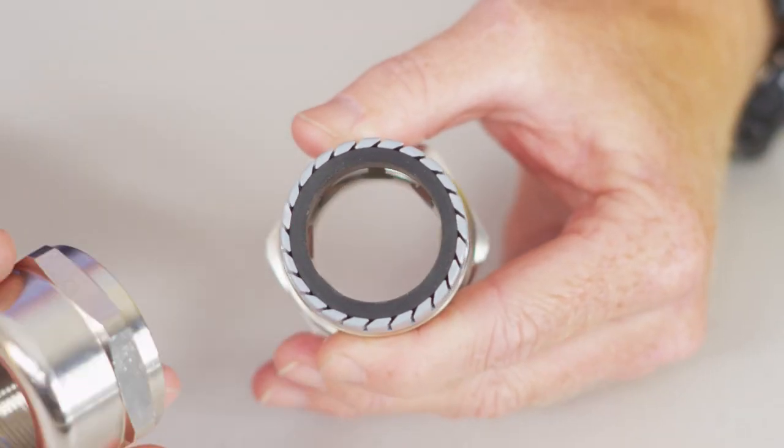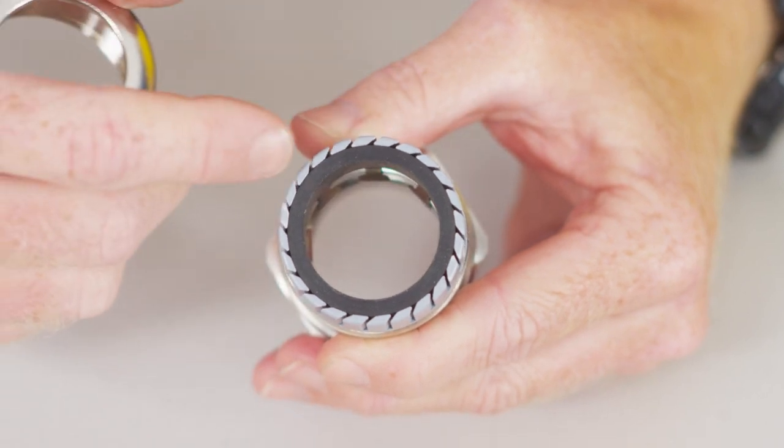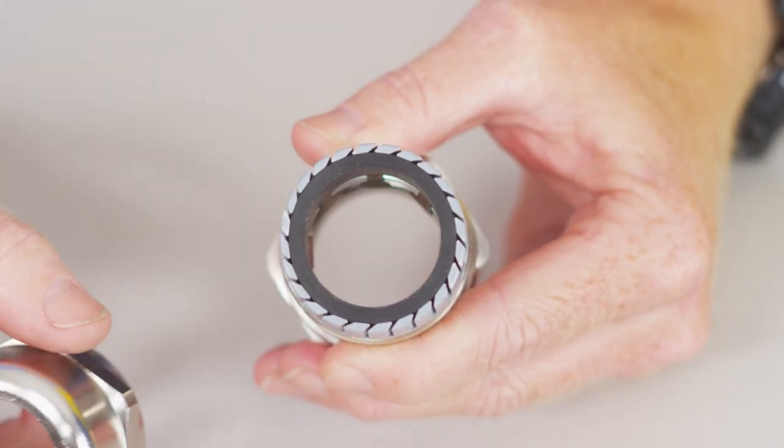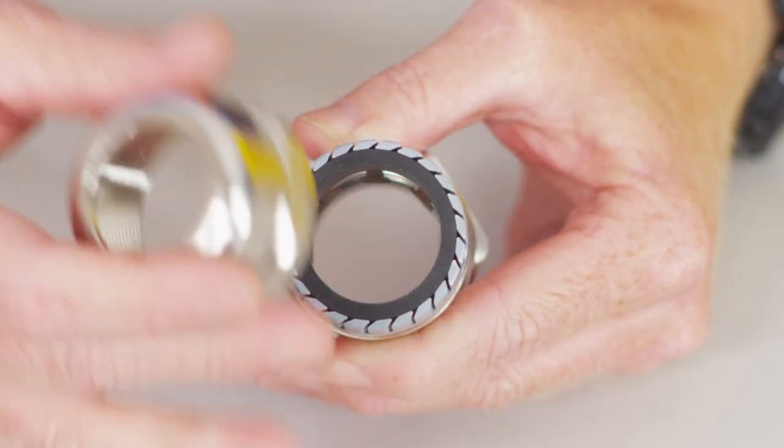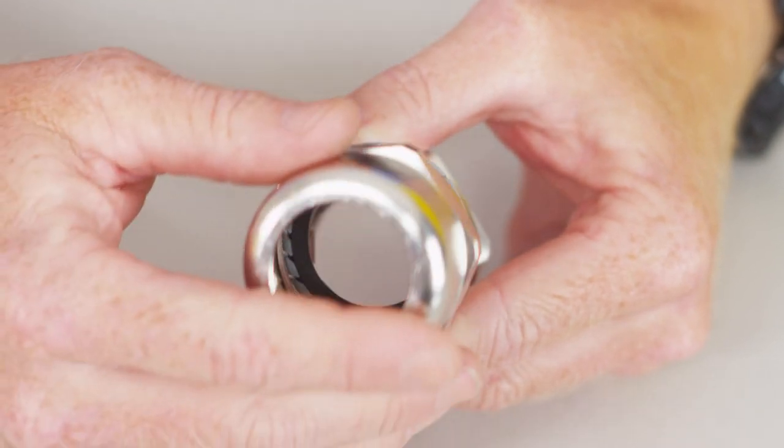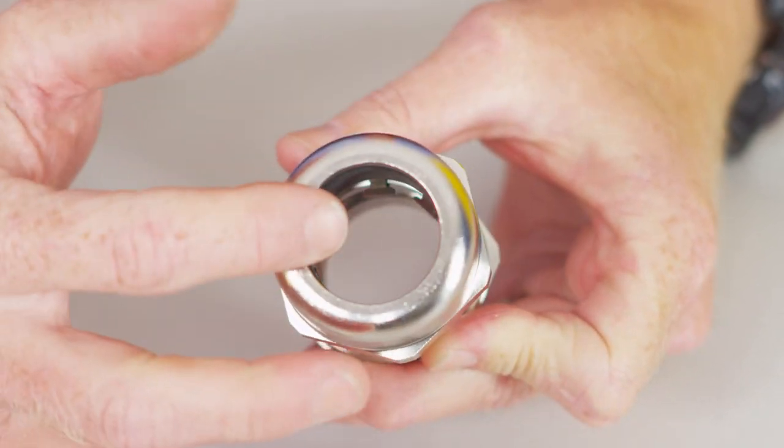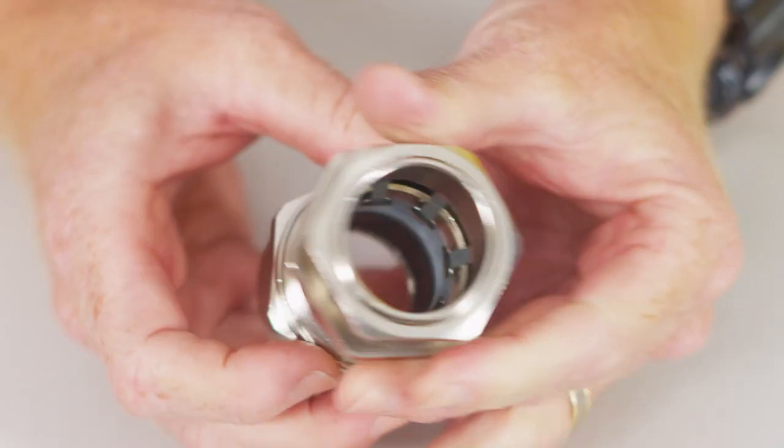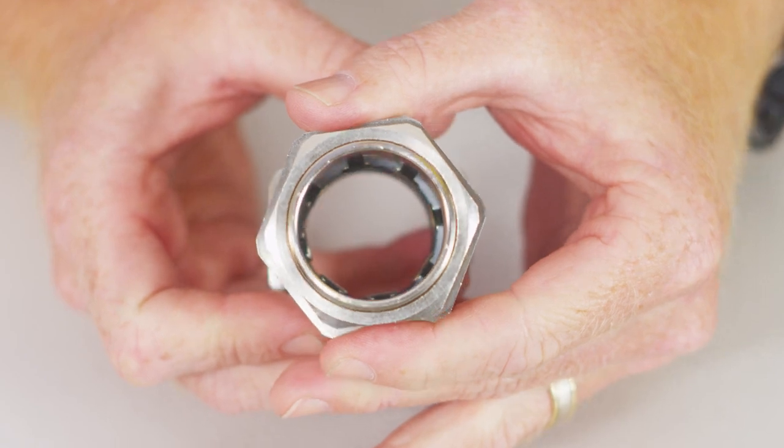Just like any other IP rated gland we have, we've got the back neoprene seal that tightens down onto the back of the cable giving an IP rating. This one here, IP68. And as we tighten up the back nut we actually compress onto that seal and which also at the same time in this EMC style gland tightens the knuckles down.